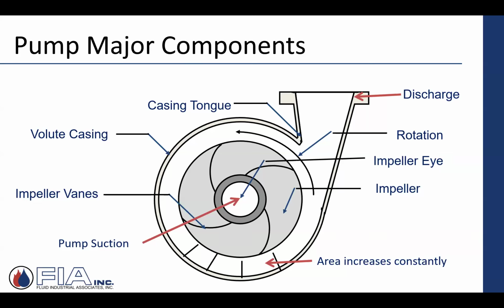So anyways, just a real simple, again, back to line drawing, but a cutaway of some of the, I guess you'd say, major components or what's going on in the business end, the pump end of a pump. So they've got a volute or a volute casing, which would be this right here, this whole outer casting. You have a pump suction, and you have a pump discharge on the top. So this would be almost an example of that.